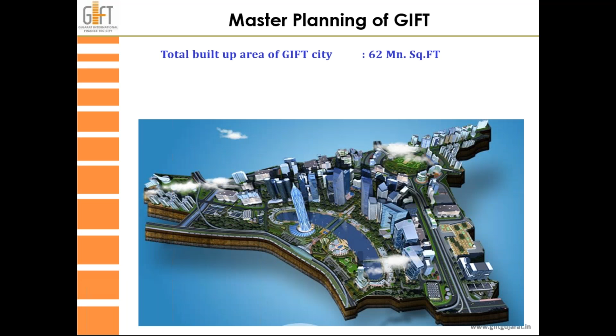When I talk about district cooling, if I need to do air conditioning for this 62 million square feet, I will require a tonnage capacity of around 270,000 tons. If I go for a non-district cooling system, the central system for each building, I may require electrical power in the range of 240 megawatts for the air conditioning of 270,000 tons.